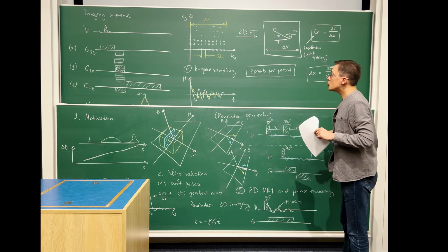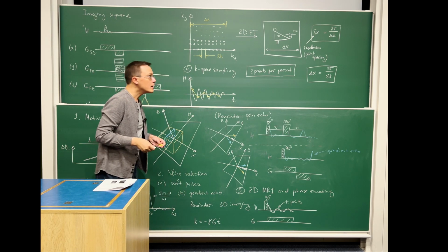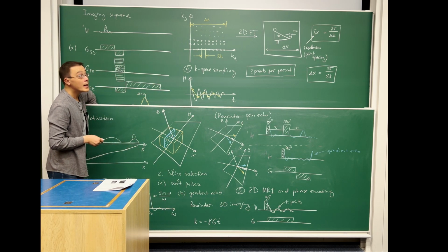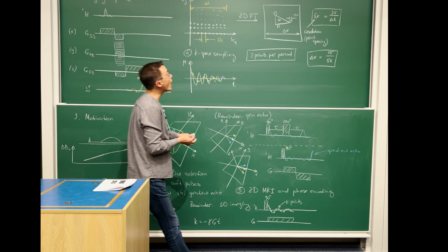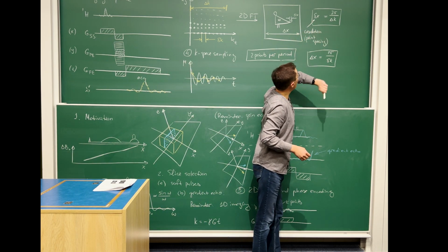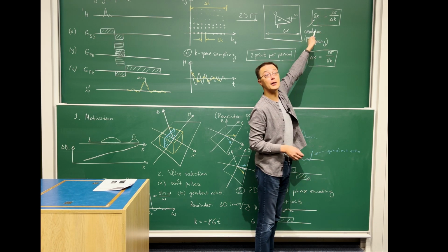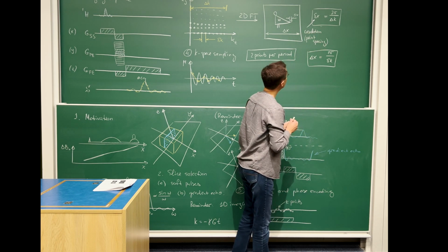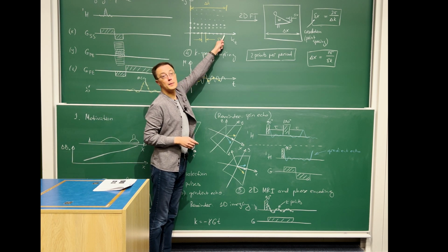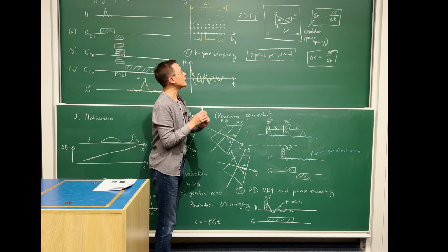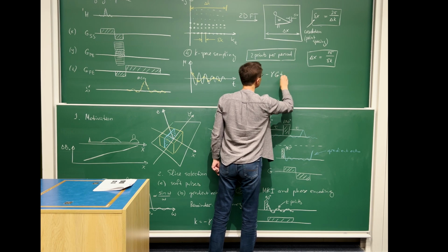And these two are quite important. Now let us think about what determines these parameters and why MRI instruments tend to be expensive. So firstly, let us think about what determines the resolution of our picture here. We want to make delta k as large as possible, because that makes for finer pixels, right? Delta k is the pixel size. But what determines delta k? Well, delta k is determined by k max, right? The maximum k that we can achieve. But what is k? K is minus gamma gt.